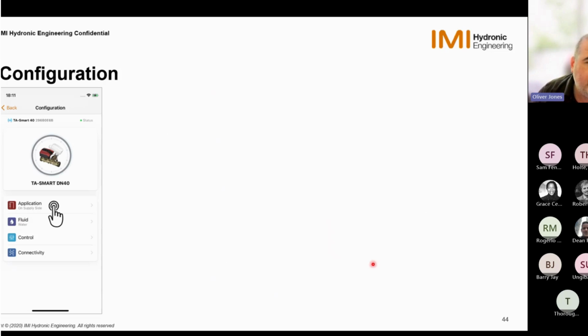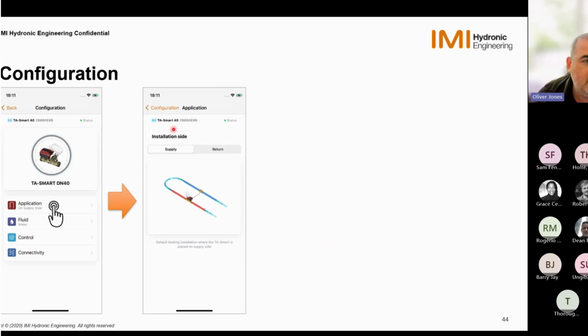So if we click the config frame, we can then go into some of the background setup. So with application, we can see that we've got the valve on the supply and the sensor is on the return. We can click return and that will switch. So we can set it up in either way, depending on how you actually want to do it.